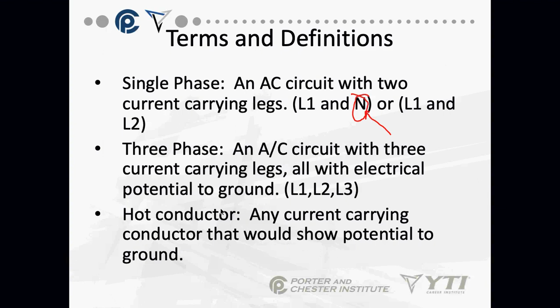If we see voltage, there's a problem someplace with the power distribution. I'll explain more when we talk about breaker panels. But we should not see any voltage from neutral to ground. If we do, somebody has screwed up someplace.